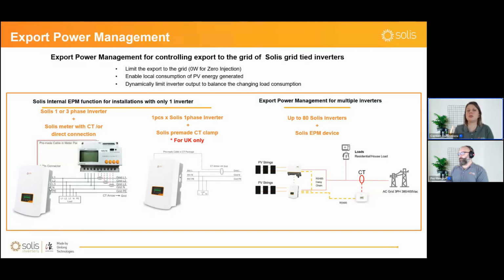But when you are in this situation where you're not allowed to export, you need to know how much is actually going out to the grid, so that you can lower the generation of your inverter. That way you can control it to either ramp up or ramp down the generation based on the way your local loads are varying, the consumption of the loads.